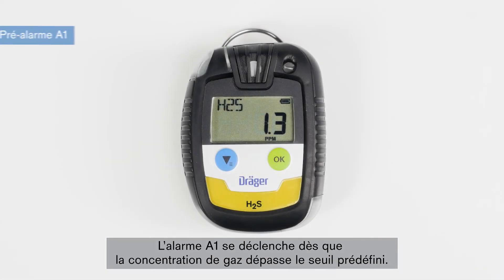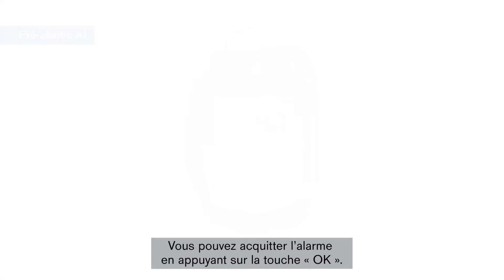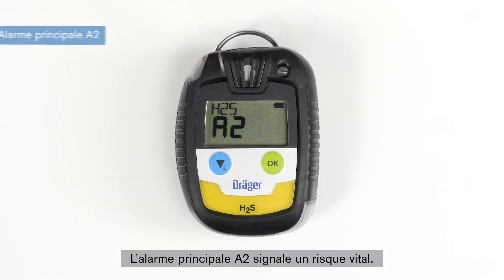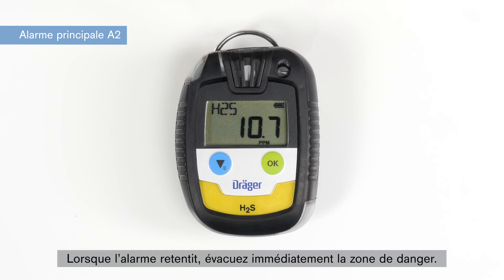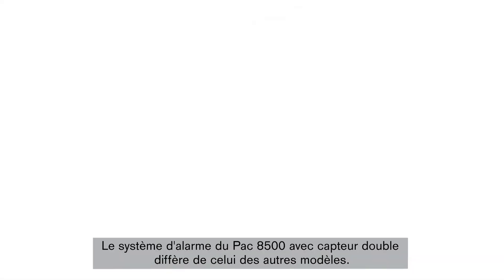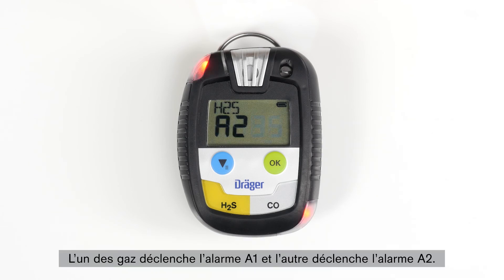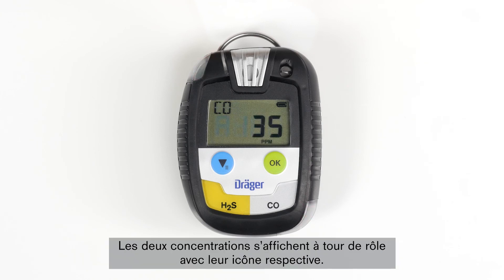The A1 pre-alarm is set off as soon as the concentration exceeds the preset threshold. There is no acute danger. You can acknowledge the alarm by pressing the green OK button. The A2 main alarm indicates danger to life. When this alarm sounds, evacuate the danger area immediately. This alarm is not acknowledgeable. The alarm on the Draeger Pac 8500 with dual sensors differs from the other models: one gas sets off an A1 alarm, the other gas an A2 alarm, and both gas concentrations are indicated alternately with the corresponding alarm icons.